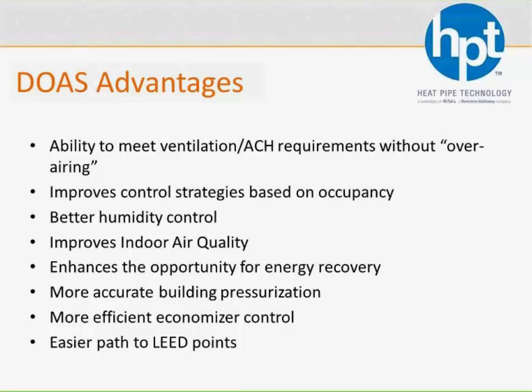So we're going to talk about the advantages. I'm completely skipping the cons because really the only con to a dedicated outside air system is that it costs more money. But like with anything, there's a difference between price and value. And if you're willing to pay a little bit more up front to save a lot more down the road, then there's lots of benefits to be had. So one, obviously, we touched on is over-airing the space. Again, if the DOAS unit is strictly handling ventilation air, then you don't have to worry about providing too much ventilation air out to the space. It's taking all that for you. So you're not providing too much air, which is unwanted, unnecessary energy. So whether we're talking about a ventilation rate that you're trying to meet or an air change requirement, it's strictly focused on giving you what you need and nothing more.